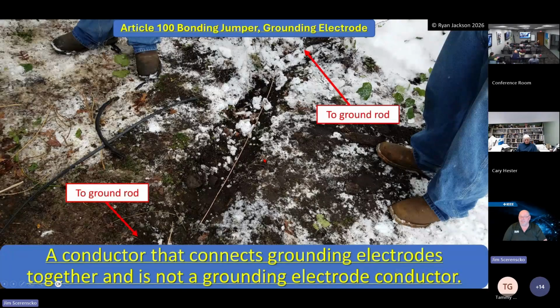This has always been a bond jumper, okay? Between the two ground rods at any building, whether it's a single family residence or a 1200 amp service, okay? But I have seen inspectors say, well, hey, that grounding electrode conductor has to be continuous with no splices. It only has to be continuous to the first rod. From the rod to the next rod, it's a bond jumper. It doesn't have to be. You can't put them under the same acorn clamp because that's designed for one conductor. But if you passed through one acorn clamp and went to the other one to make it continuous, which a lot of people do, it's okay, but you don't have to make it continuous. The grounding electrode conductor that's not allowed to be spliced is from the disconnect or wherever it terminates at the grounded conductor in the service to the first rod or first grounding electrode. Okay? That's nothing more than a bond jumper.